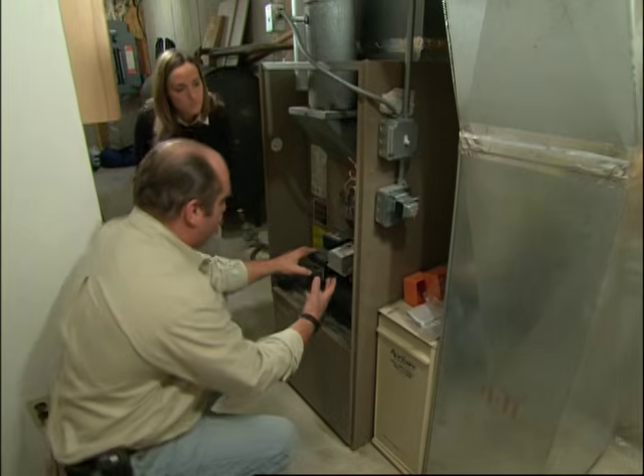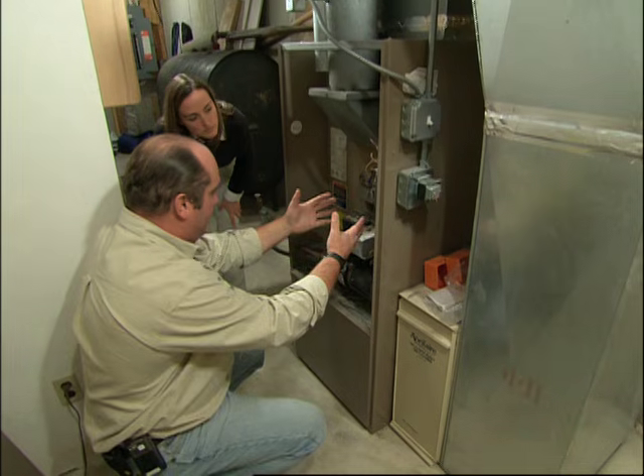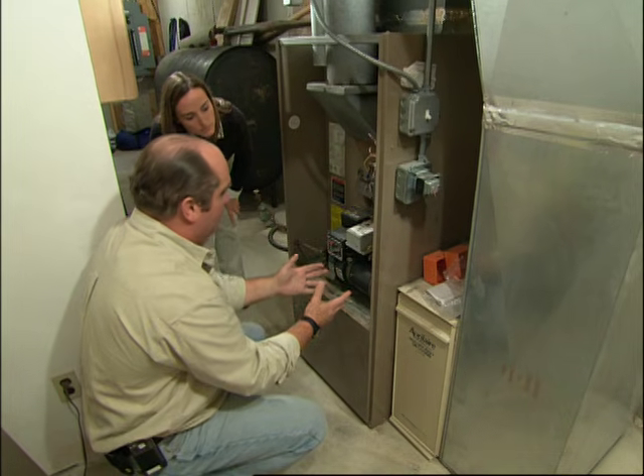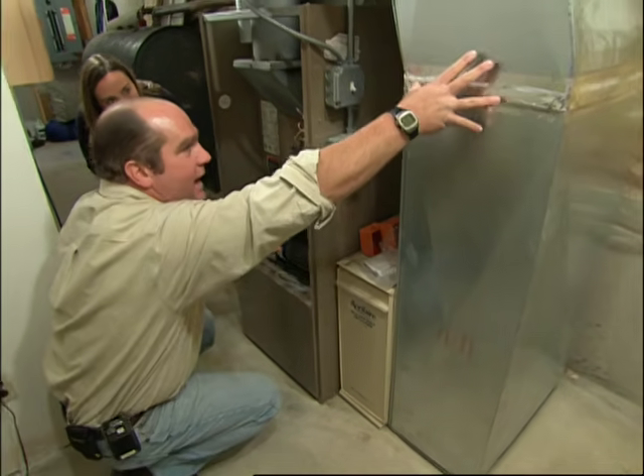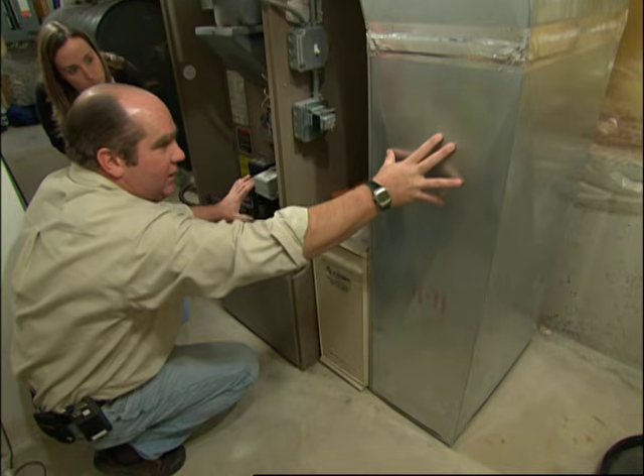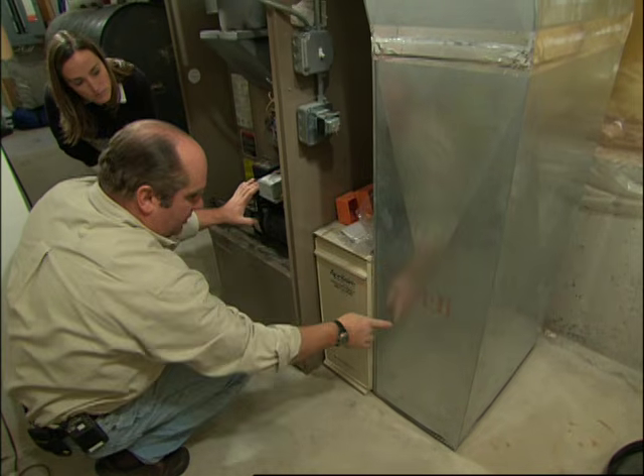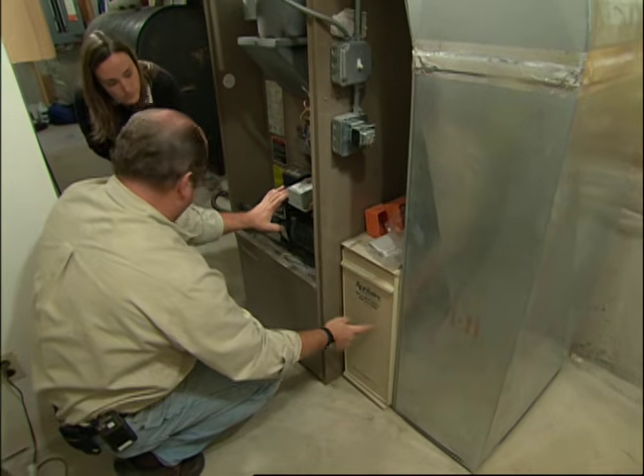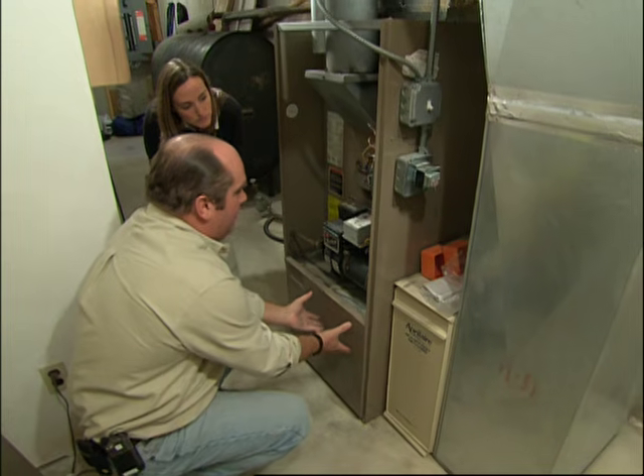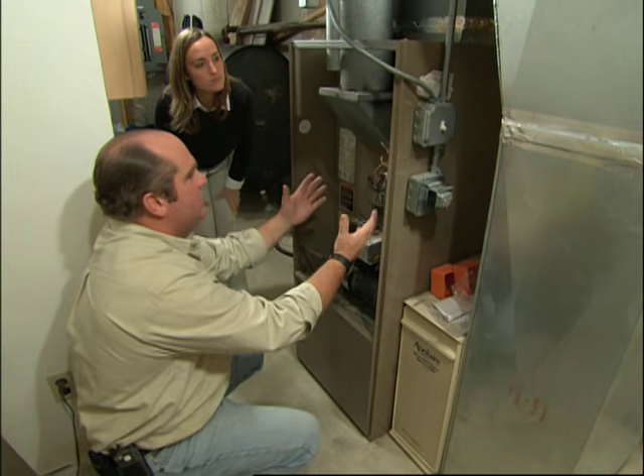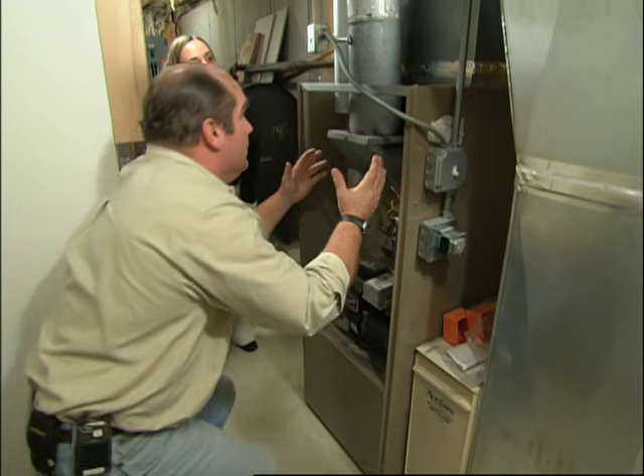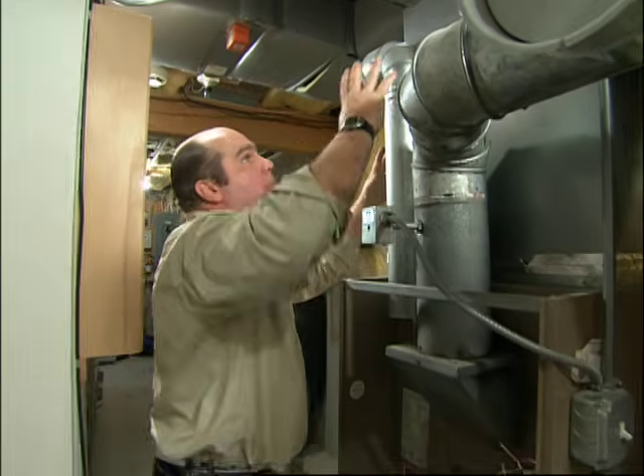When a thermostat calls for heat, the burner comes on and starts to fire. At the same time, there's a fan which comes on and pulls air back from the return air duct right here from the building. Now it's pulled across this pleated filter. I'm really glad to see that. And now the fan sits right here, and now it pushes that air up across the heat exchanger where it picks up the temperature. Now the heated air goes up into this box right here.